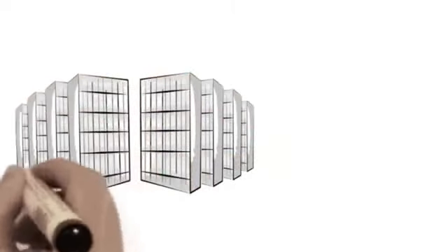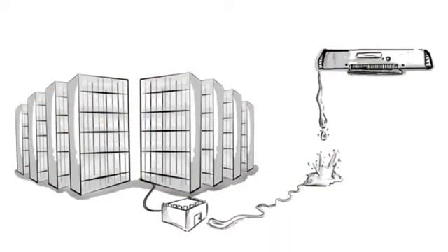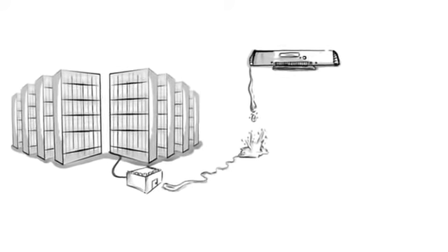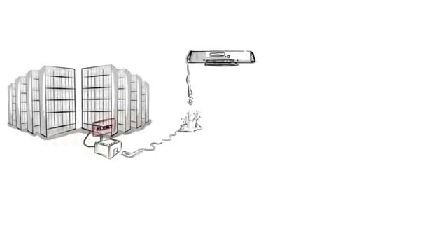Water leaks is another important environmental threat for data centers. The first source of water comes from leaking air conditioning units. A water leakage sensor should be placed under each aircon unit and under the raised floor, as water seeks the lowest point. The sensor will trigger an alert whenever water touches the sensor cable.